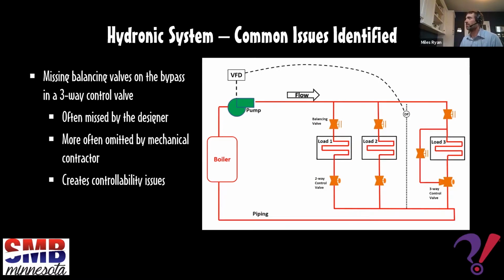Wouldn't the opposite potentially be true as well? I mean, if the flow through that load 3, when it's balanced, is not the minimum flow required for that boiler, let's say, then that bypass might have to be balanced to a lower pressure drop in order to maintain the minimum flow to the boiler.